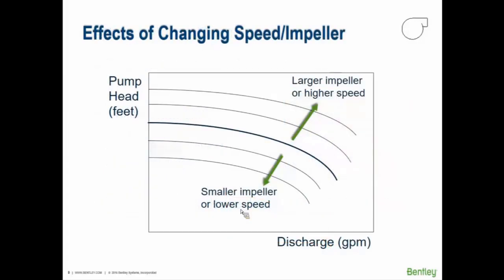When you change the speed of a pump or the size of the pump impeller, you're effectively shifting the pump curve on the axis. That's what a VFD does — it moves the pump curve up or down. There are new efficiency bell curves for each pump speed, and we'll get into more detail on that when we cover extended period simulations.